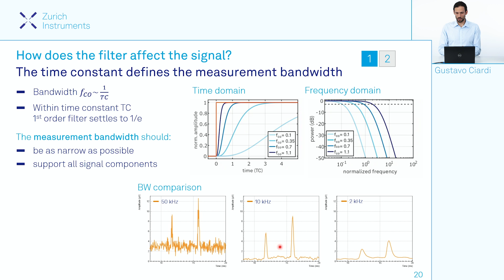The second knob we can turn to affect our signal-to-noise ratio is the filter order, which simply means how many low-pass filters with the same bandwidth I'm cascading after one another. As I increase the filter order, the roll-off curve of the filter steepens, getting closer to a brick wall filter. The trade-off is that the signal needs more time to settle to its new value, so for an accurate measurement we need to wait longer. For these reasons, the filter order should in general be kept as low as possible, to minimize settling time while still ensuring suppression of spurious frequency components.